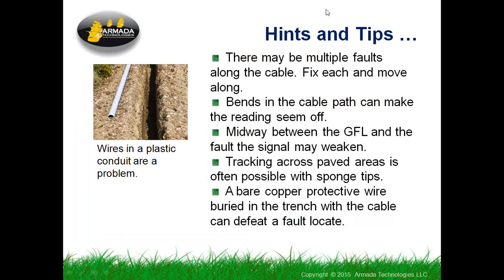Some of the tips on there were actually pretty good and interesting. I'm going to reiterate some of those. But finding multiple faults along the cable: when in doubt, keep going. If you're going along and you find a fault, you could fix that fault and look for another one, because when people are going out looking for main faults, cuts even, you will find some smaller faults along the way. So you need to fix them and clean them up as you go. So keep going and move along.